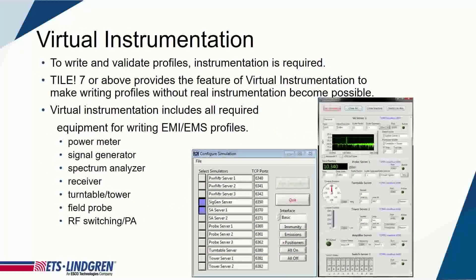The virtual instrumentation feature includes a very well-written LabVIEW simulator that can be used to test a profile before you take time from equipment or a chamber in your lab. You can actually set up virtual signal generators, towers, turntables, and power meters and link them together. TILE will actually talk to them and believe it's talking to an Ethernet instrument — it doesn't know any different. It's very comprehensive, and we have a separate manual for operating it. I use it to simulate a spectrum analyzer that's receiving a signal, which is a good way to get your feet wet and learn the basics.